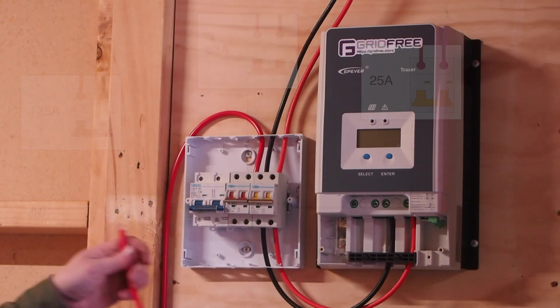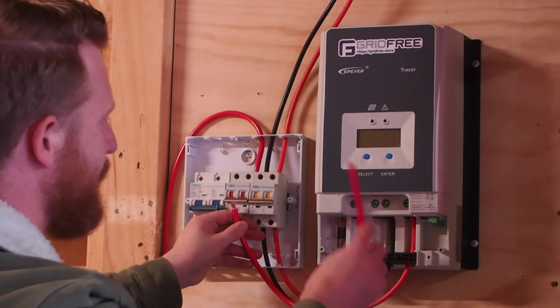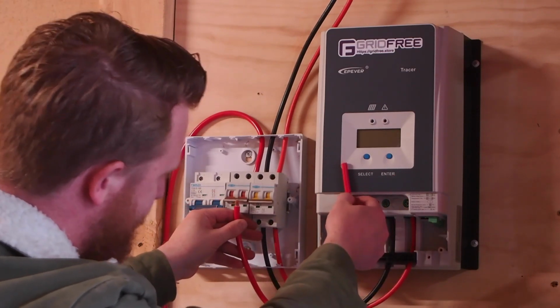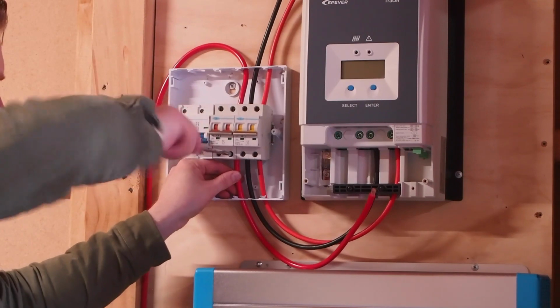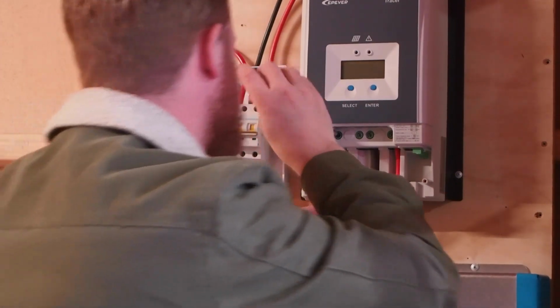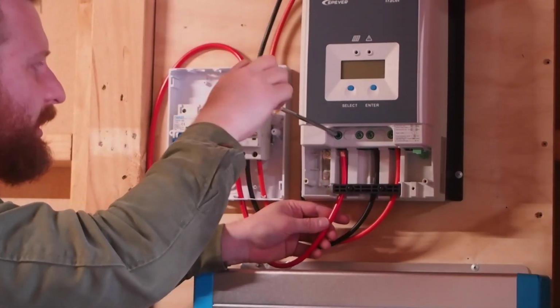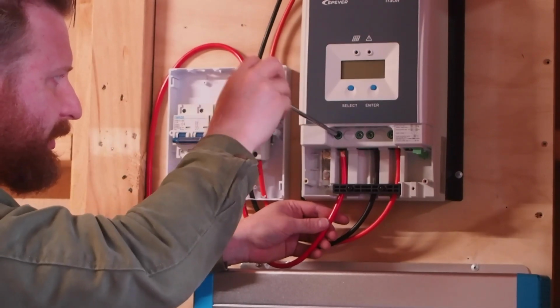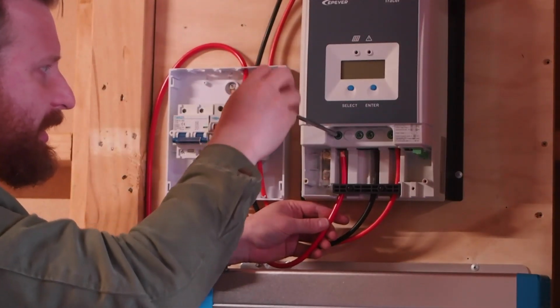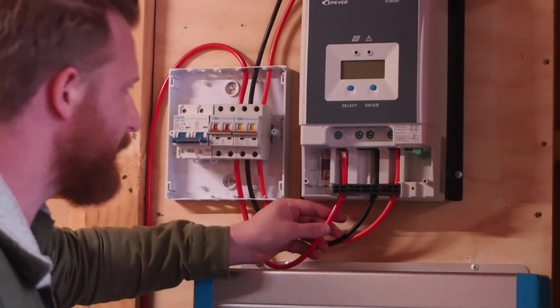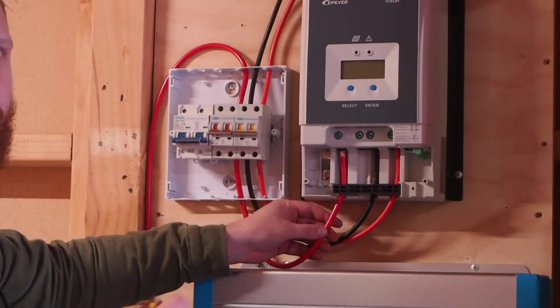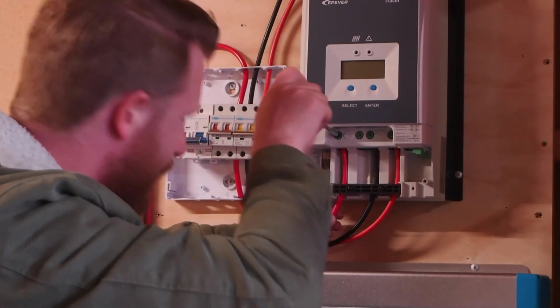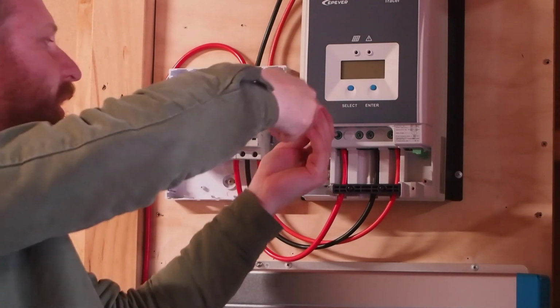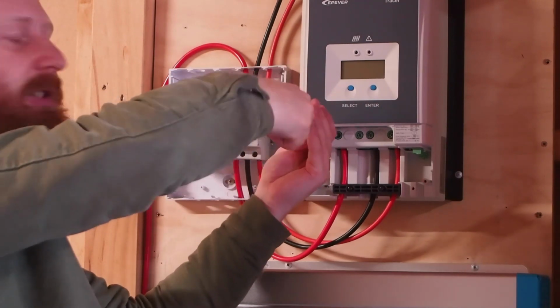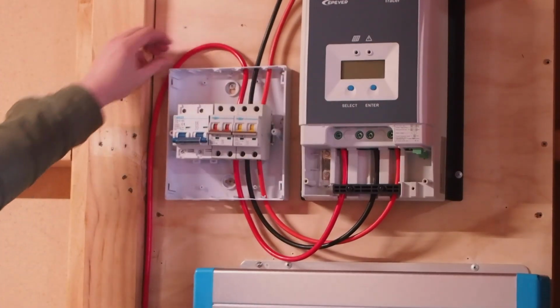Now just doing this one, we're going to do the same thing as before, just making sure we get the right length on this. When you're putting these cables in, you want to make sure that these are fully unscrewed, which means the clamp is in the furthest down position, which means it's going to be the easiest to get the cable between the clamp. Again, making sure that we're clamping on the conductor of the cable and not the insulation. Alright, that's our positive run done.